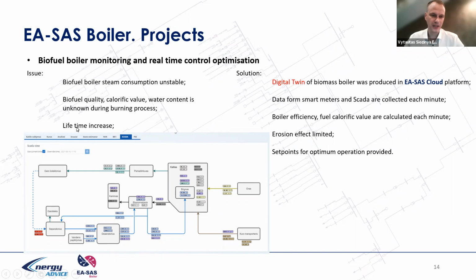And we require increased lifetime or time between maintenance. So we install a digital twin for the biomass boiler. It's the same platform, with data collected each minute and calculated each 5 minutes. And finally, what was optimized was the operation: grate movement, fuel supply, primary air control, and the erosion effect was limited. Set points were provided for the operators, so the boiler control system was operated by optimum set points from our cloud solution digital twin model.